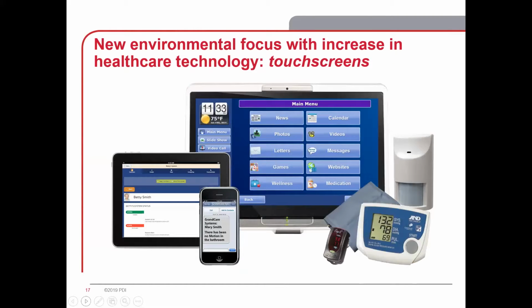One of the things that we're seeing a lot of now in healthcare is the increase in healthcare technology and touch screens. The reason I bring this up is that typically the touch screen technology usually cannot use some of the more standard disinfectants. So you have to make sure that when you are dealing with equipment with touch screens that you do read the manufacturer's instructions for use as to what types of chemicals can be used on the actual touch screen itself. A lot of times it's simply just plain 70% isopropyl alcohol, and you cannot use bleach or quaternary ammonia type disinfectants on the touch screen.